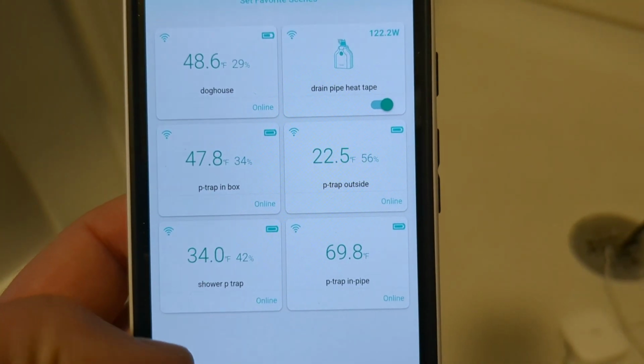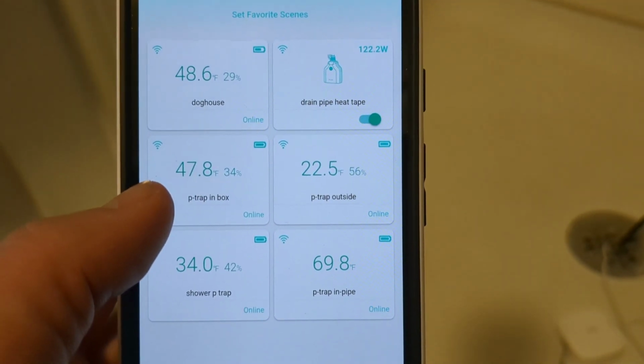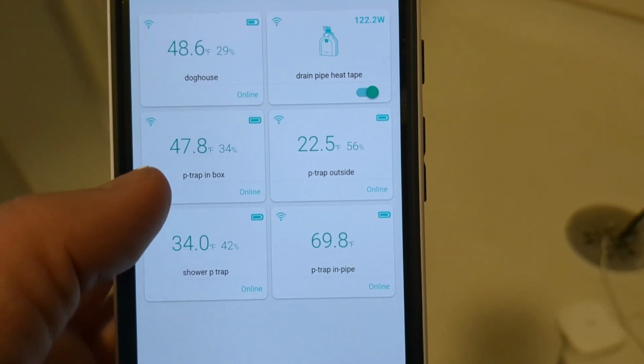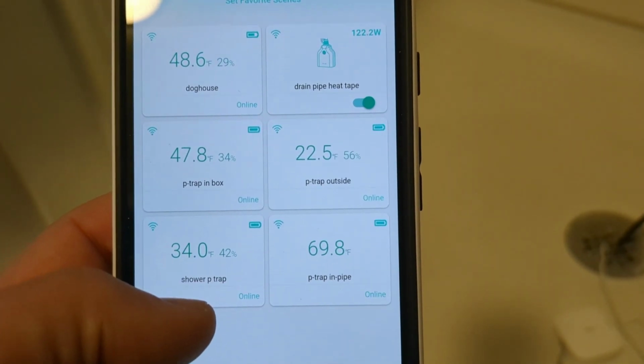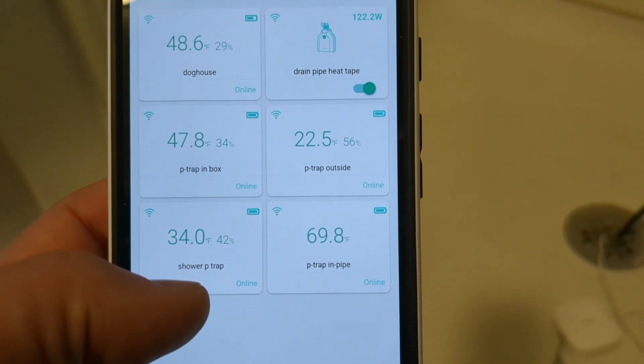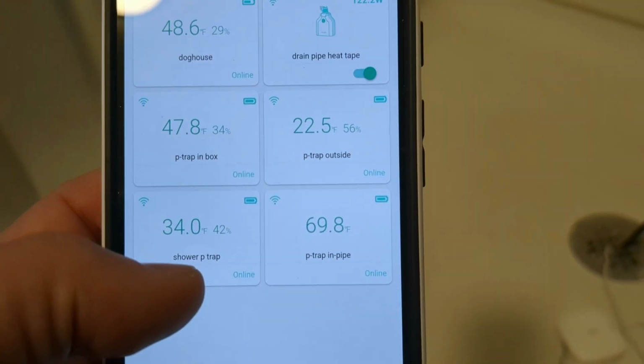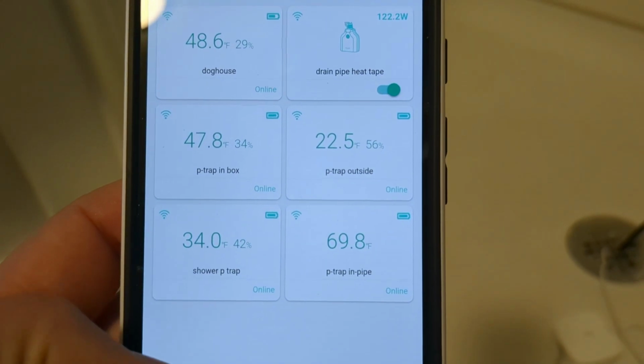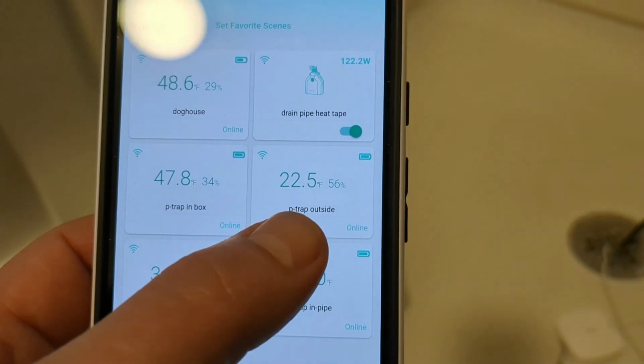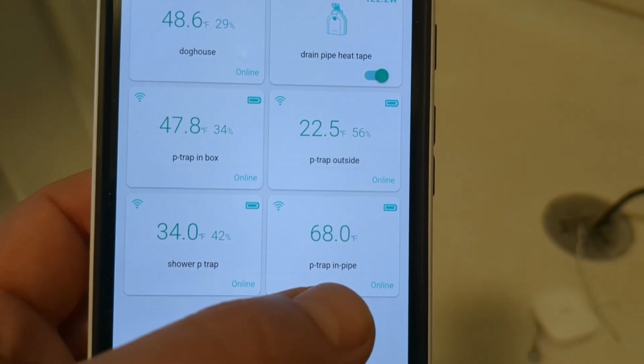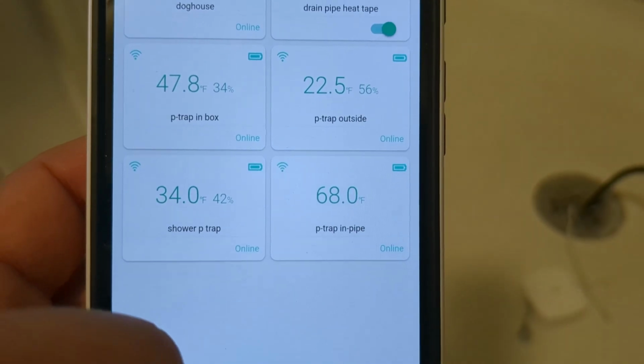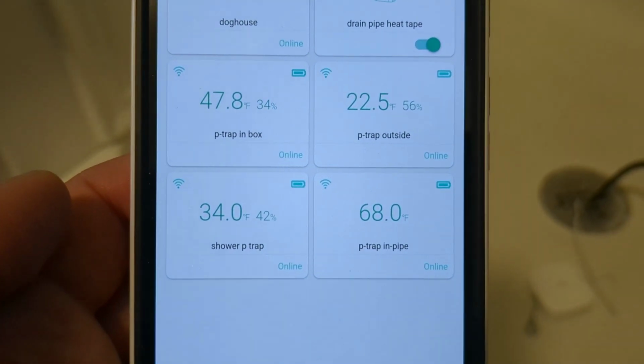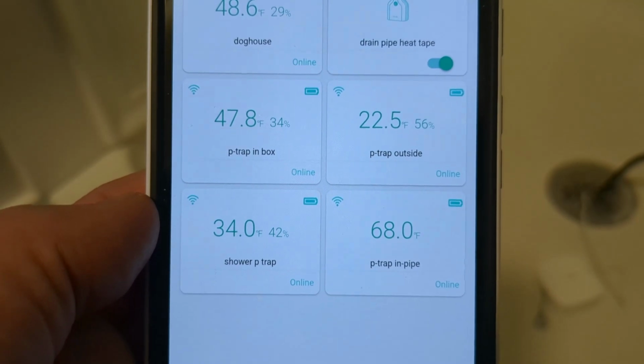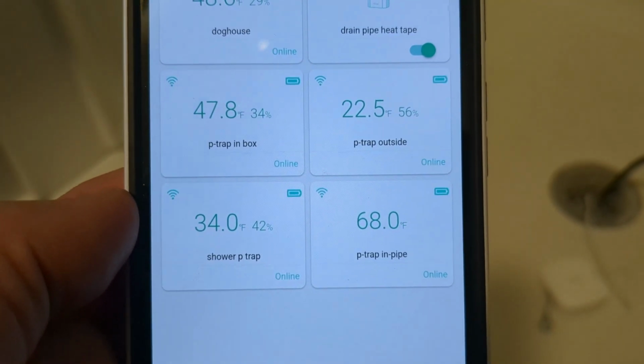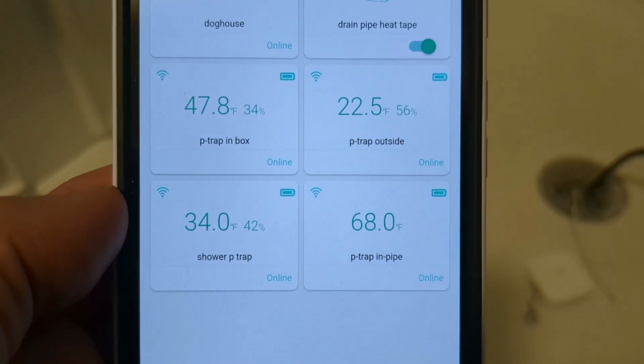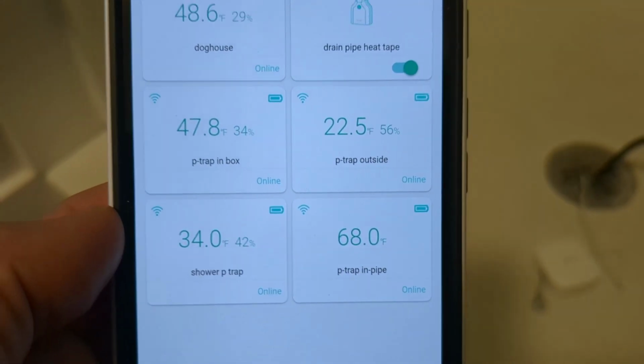And so you can see a few sensors here. We've got that sensor, 47.8 degrees, is the sensor we added inside of the box. This sensor here that's reading 34 degrees is the one that's attached to the pipe and wrapped in a thin layer of insulation. And then this is the temperature outside, so it's 22 degrees outside. And then inside the actual water is reading 68 degrees, which is really good. That's not going to freeze anytime soon. I think this is a success. I think we can call that a win. And we'll leave the sensor in for a few weeks and see if we're still maintaining a nice 68 degrees of the water in the P-trap.